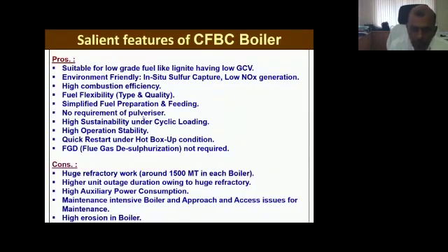Then, because of this refractory, the higher tonnage, and the configuration and arrangement of the major pressure parts, there is a major issue regarding approach and access for carrying out the maintenance activity. This further extends our outage time, and there is a lot of criticality in doing the maintenance.